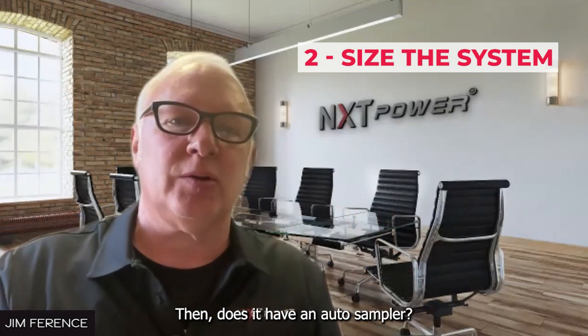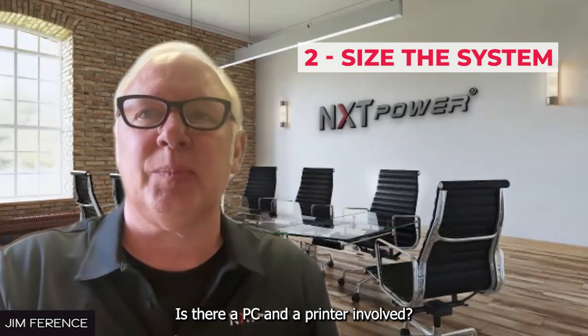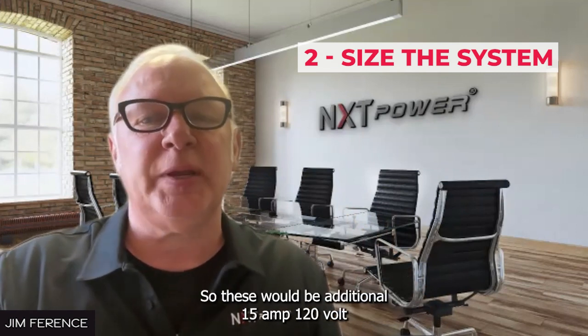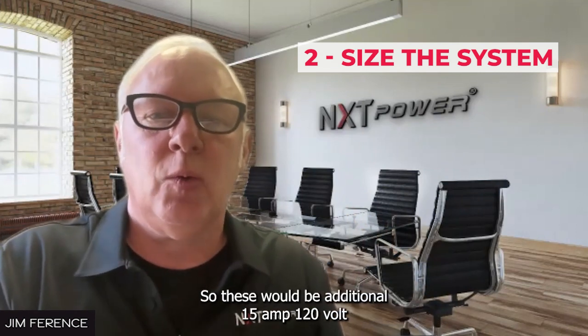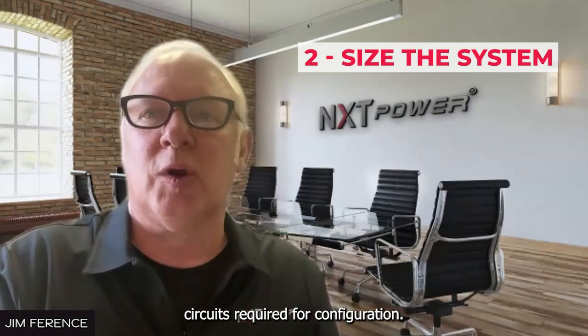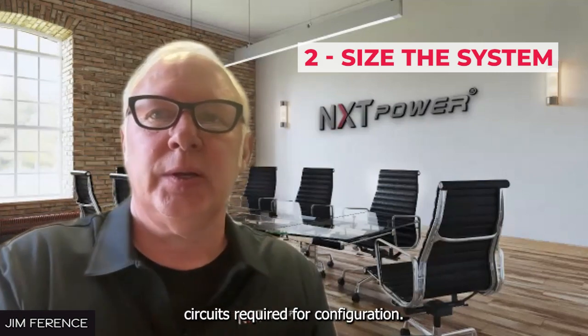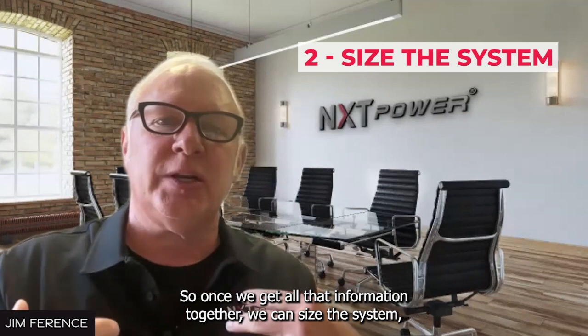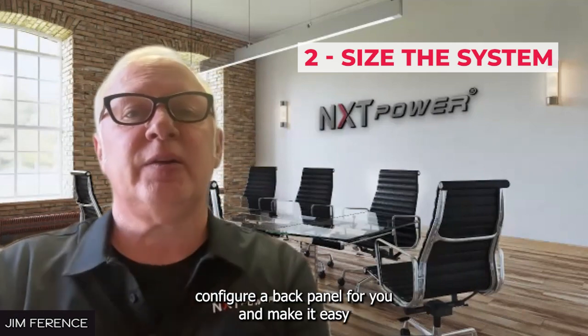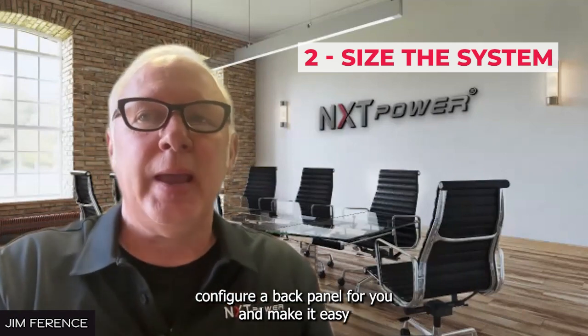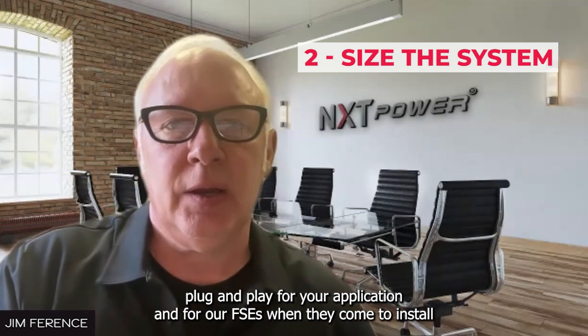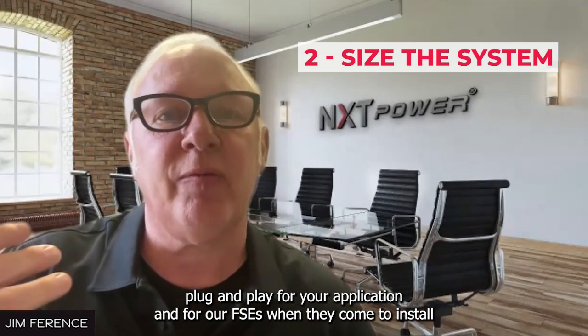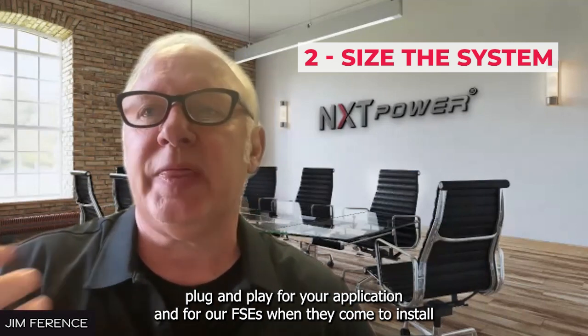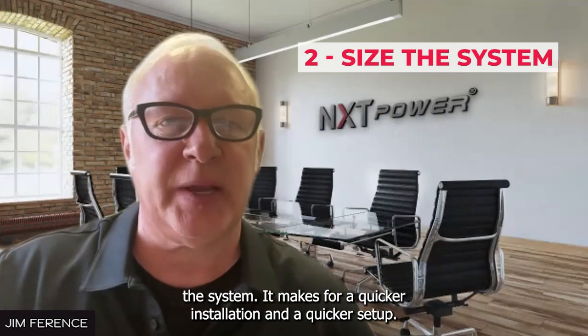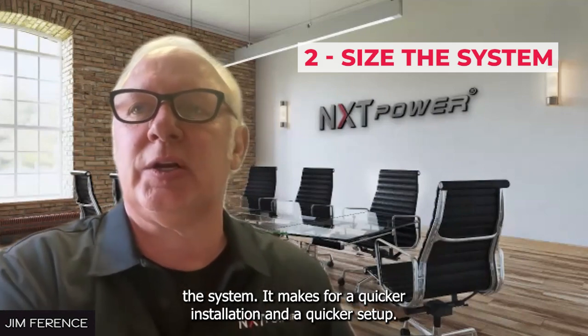Then, does it have an auto sampler? Is there a PC and a printer involved? These would be additional 15 amp, 120 volt circuits required for the configuration. Once we get all that information together, we can size the system, configure a back panel for you, and make it easy plug and play for your application and for field service engineers when they come to install the system. It makes for a quicker installation and setup.